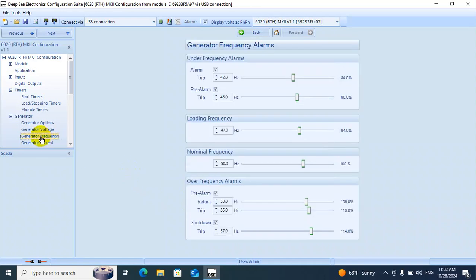Above that, we are coming to the frequency. Both of them are alarms. On loading frequency, when we're applying load to the generator, the frequency will go down. As the lowest amount, if it comes down to 47, the generator will shut down. This is the nominal frequency. When we want to convert it to 60 Hertz, we have to change it from here and make it 60. For example, like this.